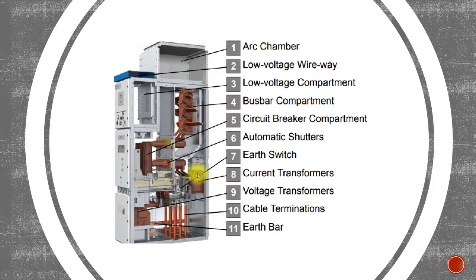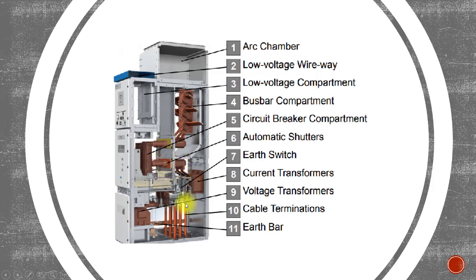Number eight is the current transformer. You can see the cable coming in, going into the CT, and then coming out. The current transformer is connected in series, so you will find two connections — one incoming and one outgoing. You can recognize a current transformer from a voltage transformer because the CT has two terminals since it is in the current circuit and must be in series.